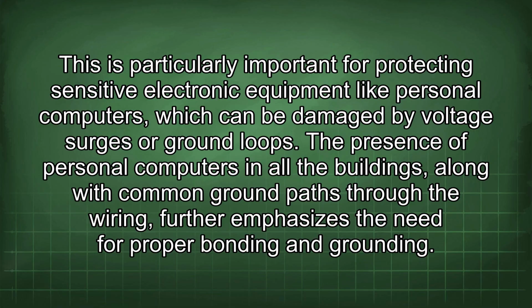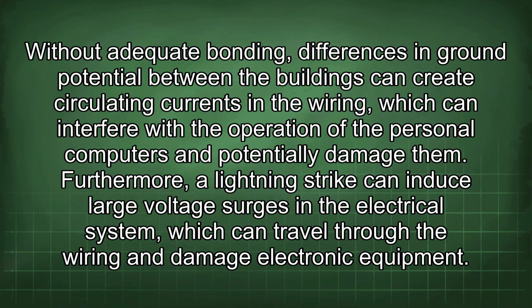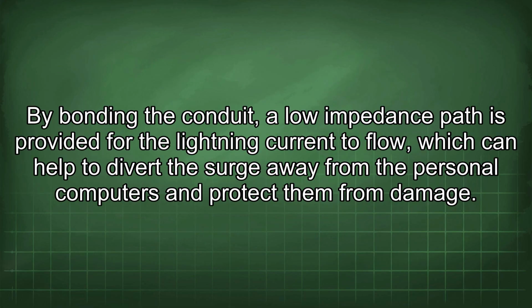The presence of personal computers in all the buildings, along with common ground paths through the wiring, further emphasizes the need for proper bonding and grounding. Without adequate bonding, differences in ground potential between the buildings can create circulating currents in the wiring, which can interfere with the operation of the personal computers and potentially damage them. Furthermore, a lightning strike can induce large voltage surges in the electrical system, which can travel through the wiring and damage electronic equipment. By bonding the conduit, a low impedance path is provided for the lightning current to flow, which can help to divert the surge away from the personal computers and protect them from damage.